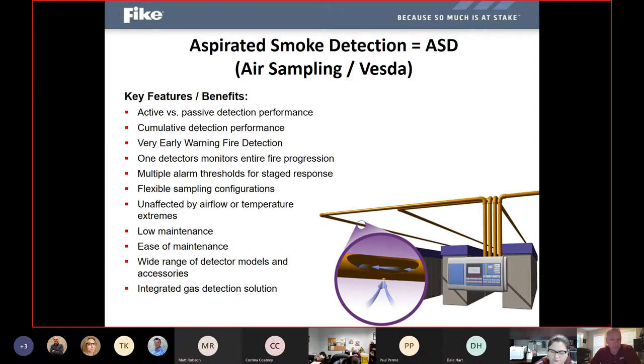We're going to actively bring air from a big area back into our sampling chamber and detect very trace amounts of smoke to achieve very early detection. So, kind of along the same way as video detection, instead of waiting for smoke to reach a detector and to concentrate to upwards of 2.5 or so, or 2 to 5% obscuration, we can bring very trace amounts of smoke from an area back to our detector and achieve much earlier and much more sensitive detection to trigger a smoke detection alarm, or even a suppression system, much earlier in the process than waiting for that smoke to develop. So a very wide range of products, from very early warning air sampling detection, is available through Fike Corporation by Xtralis, formerly known as VESDA.